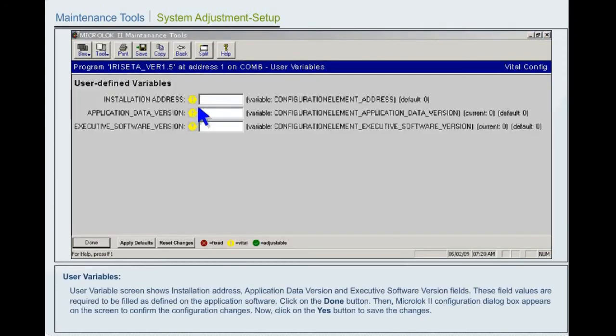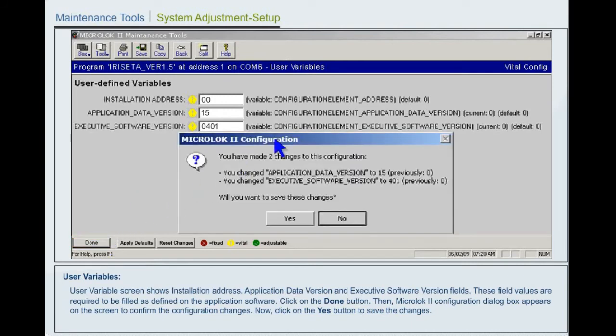User Variables. The User Variable screen shows installation address, application data version, and executive software version fields. These field values are required to be filled as defined in the application software. Click on the Done button. Then the Microlok II configuration dialog box appears on the screen to confirm the configuration changes. Now click on the Yes button to save the changes. Click on the Next button to continue.